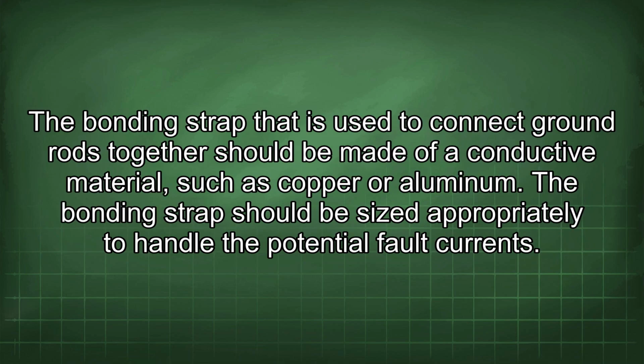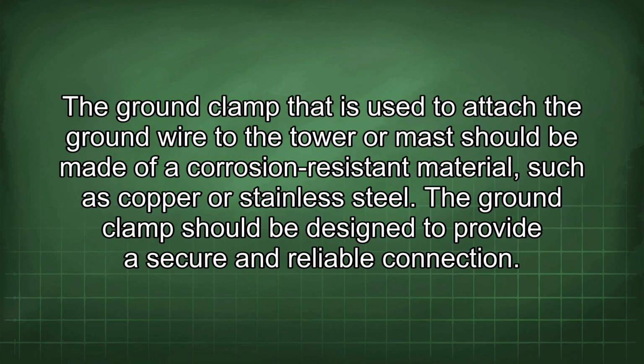The bonding strap that is used to connect ground rods together should be made of a conductive material such as copper or aluminum. The bonding strap should be sized appropriately to handle the potential fault currents. The ground clamp that is used to attach the ground wire to the tower or mast should be made of a corrosion-resistant material such as copper or stainless steel. The ground clamp should be designed to provide a secure and reliable connection.